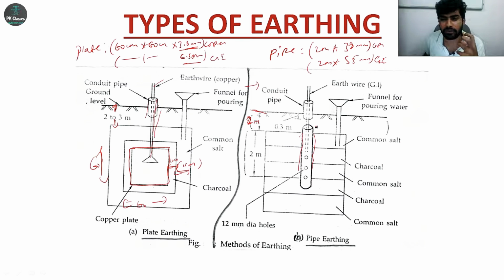Next we'll see pipe earthing. Pipe is placed vertically down into the earth about 2 meter from the ground level, right? And layer by layer charcoal and salt is placed to increase the conductivity of the soil and reduce the resistance of the soil. There is a funnel for pouring the water in the summer season. If suppose water is poured here, so water content will be there, means definitely conductivity increases, so resistance decreases. See why? Because of this common salt, charcoal or water here, if the resistance decreases, whatever the fault current directly goes to earth, right?